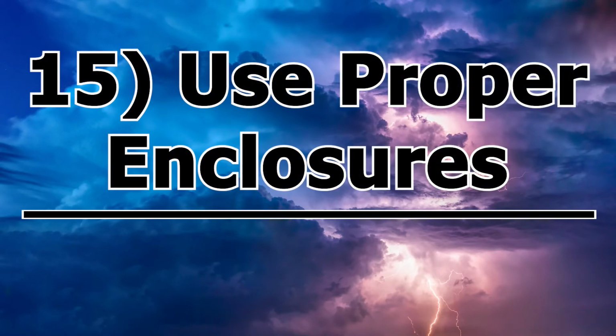Tip number 15: use proper enclosures. There are all sorts of places you might build a panel or electrical box. If you're putting it outside, make sure it can stand up to the elements. If you're putting it somewhere hazardous, like around gasoline or somewhere that might explode, make sure you get one rated for explosive environments. Also, if using a metal enclosure, make sure you ground it. If using a plastic enclosure, make sure the insulation rating can hold up to whatever you're putting in it.